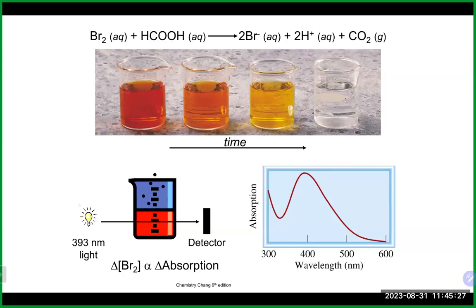How it basically works is, you set your wavelength to a specific wavelength. It shoots through your sample and reaches the detector. We usually measure one of two things, either absorbance, which is how much light gets absorbed by the sample, or percent transmittance, which is basically the ratio of light that went in to the light that reached the detector. Most of the time we measure absorbance, which again is based on the color of the solution.